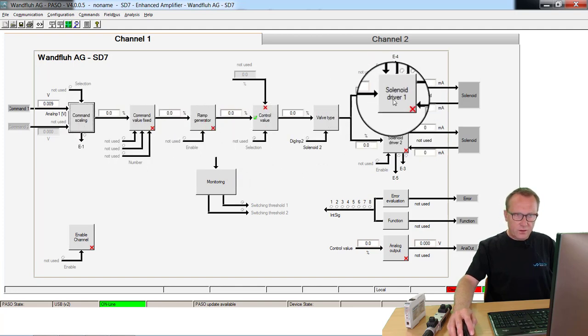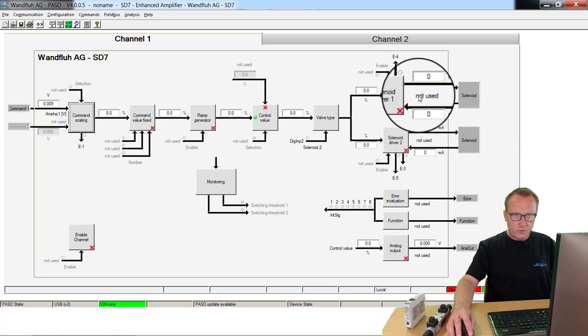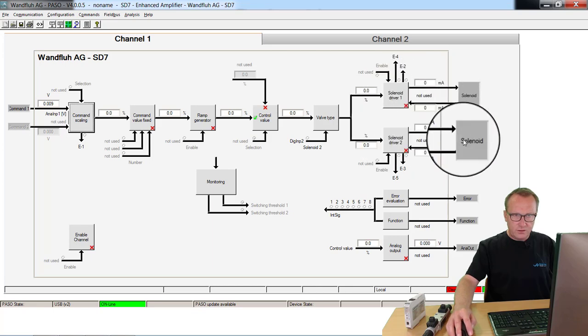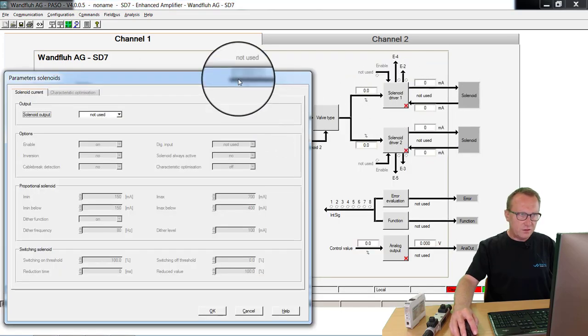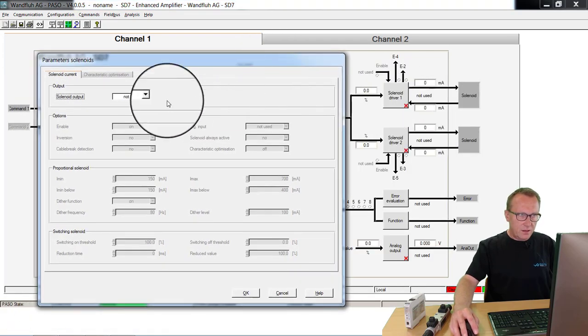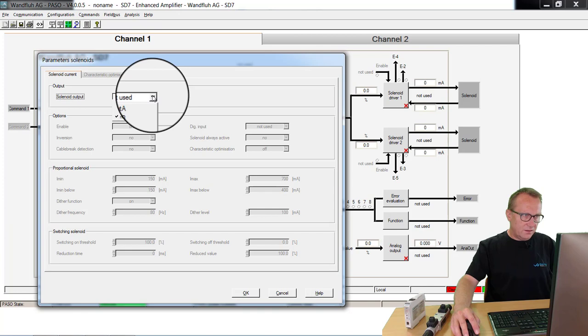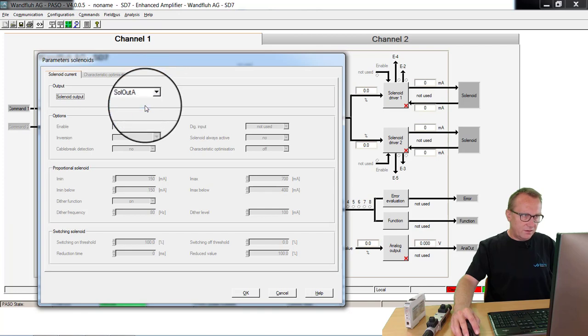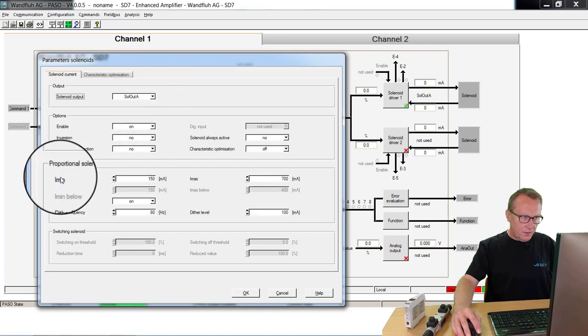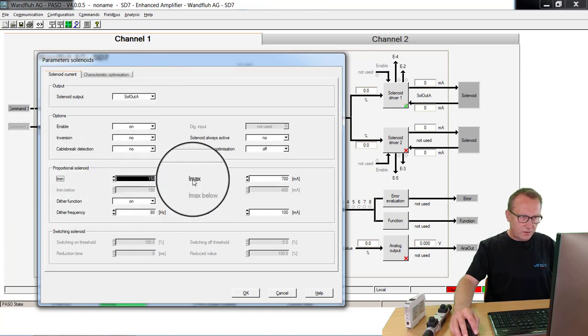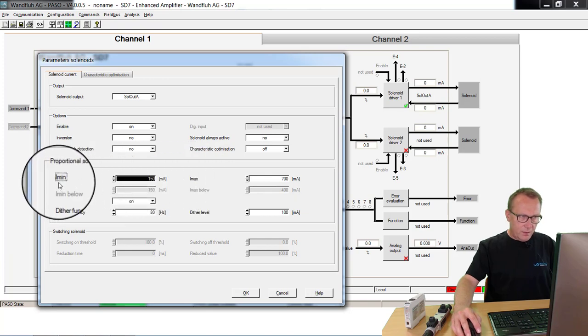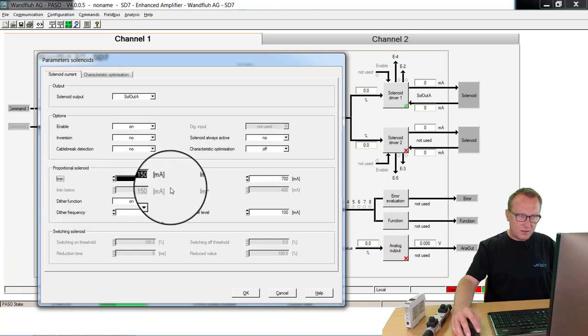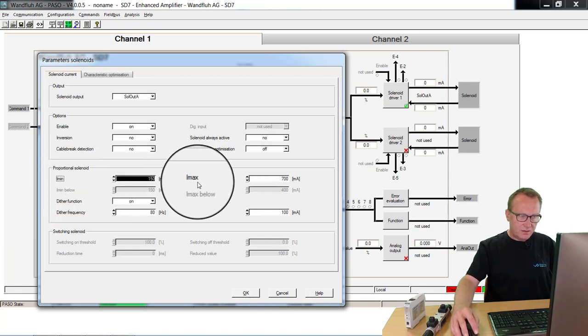We go to the output. Solenoid driver 1 and 2. This is for one direction, this is for the other direction. We start here. I say here this is solenoid A. Now I can adjust the I-minimum and I-maximum. The minimum current I have if the internal value is 0%. The I-maximum I have if the internal value is 100%.